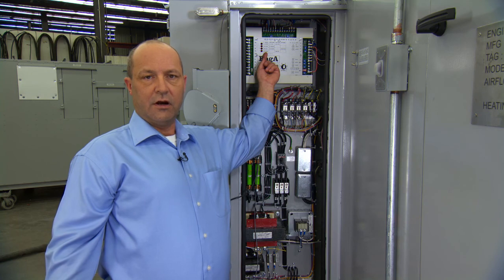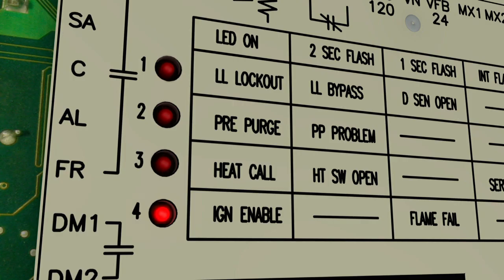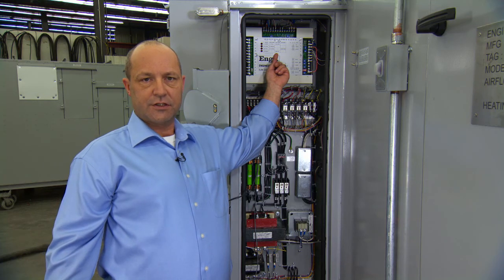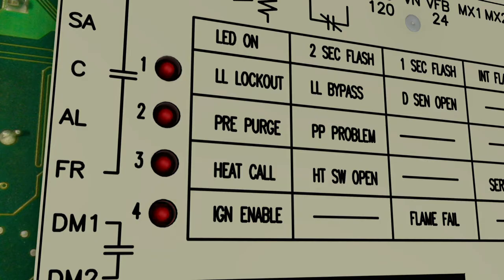Number 4 light, on steady. This is on when the ignition is enabled. 1-second flash. This will happen when there is a flame failure. To reset, turn the service switch in the unit control panel off and back on.